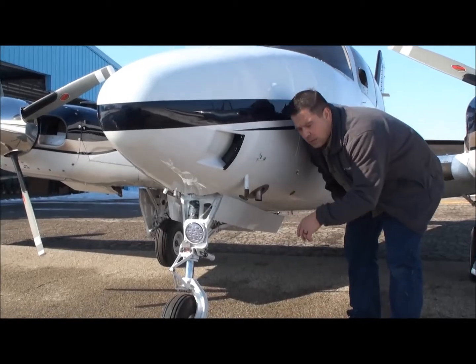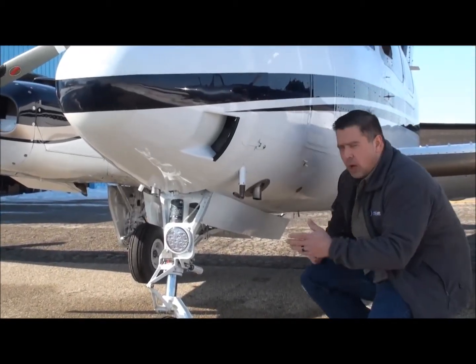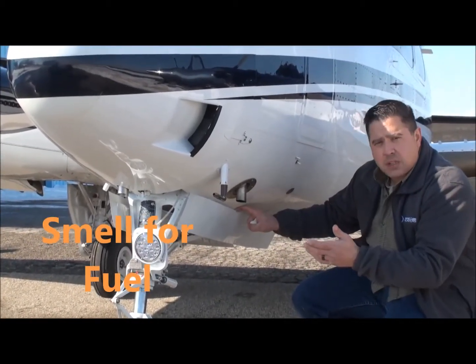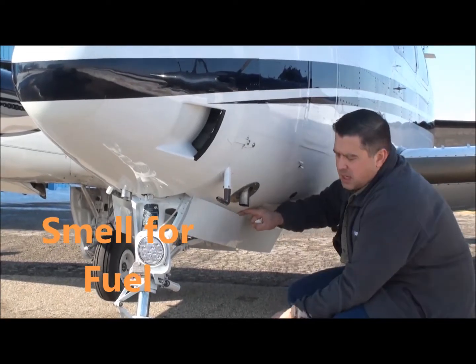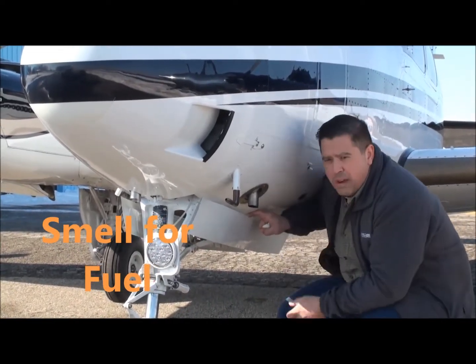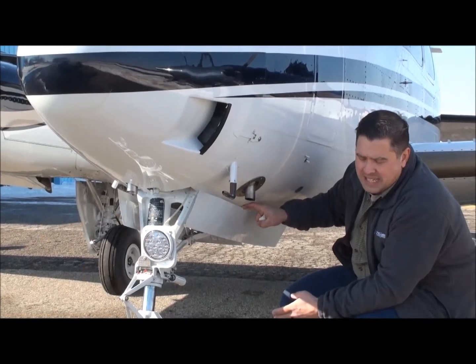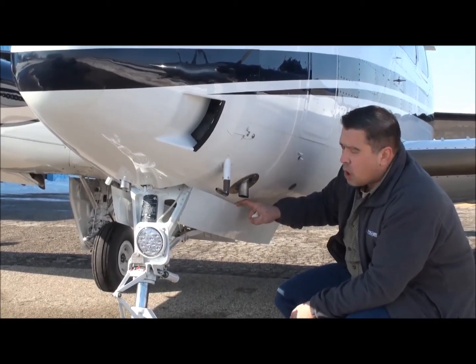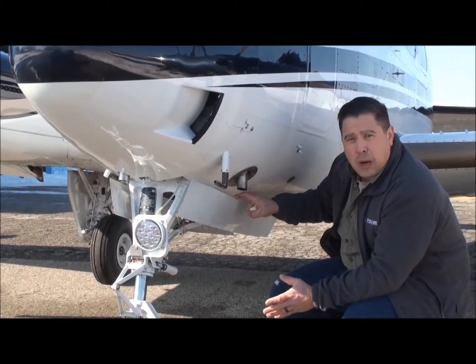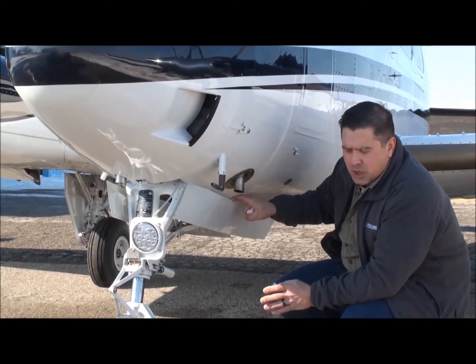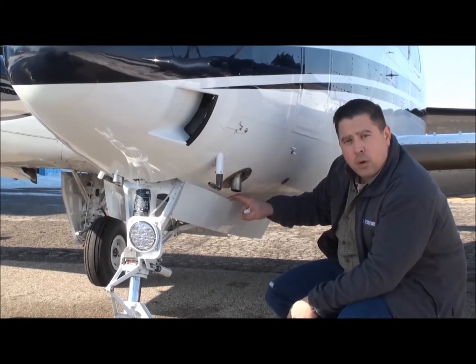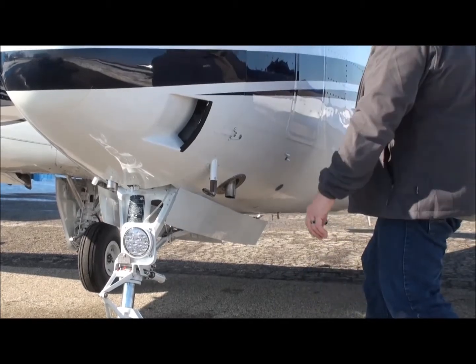But even in low heat, what you would do for fuel, we all know what avgas smells like, or jet fuel, whatever the installation. You're going to whiff for fuel, and you're going to smell that distinct odor. And whether or not it's a good output of fuel, the spray pattern's bad, good, you still need to have fuel into that system. Low temperature.